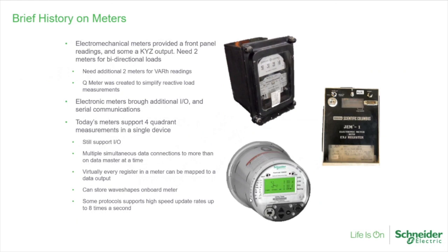They still have legacy support for I/O. You can have multiple simultaneous data connections to more than one data master at a time. Pretty much every register in the meter can be mapped to a Modbus or DNP output. A lot of devices support 61850 as well now. They can store wave shapes on board the meter. They can be supported natively in their protocol, or they can go into COMTRADE. And then some protocols support higher update rates. So Modbus in the meter is like 1 second.